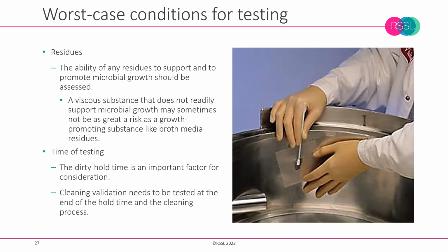Now, I mentioned worst case conditions for testing. And here we need to ensure that we're undertaking the sampling for cleaning validation at the end of the cleaning process, immediately at the end of cleaning, so that we're getting a more direct assessment of the ability to effectively clean using the defined process. It's also important, though, that we're not starting the cleaning validation until we've reached the point of the maximum hold time. And that's because of that point I mentioned earlier about dirty equipment being harder to clean and soil becoming more difficult to remove, and also the greater chance of microbial contamination build up.